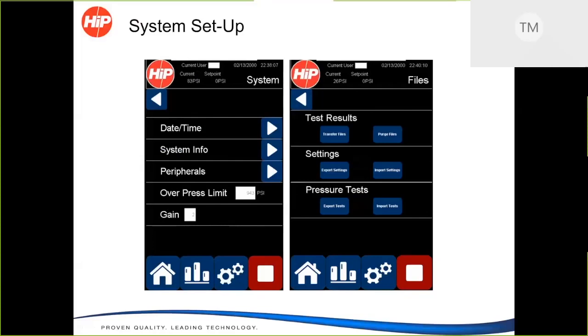If you have a very large volume, set that gain to a higher number, and we'll speed up the air regulation so we can build up pressure faster. So think of gain as a balancing act of the likelihood of overshooting versus the speed to build pressure. If you're overshooting your test value, you're going to want to decrease your gain value. If it's taking too long to build pressure to your desired set point, you're going to want to increase your gain number.